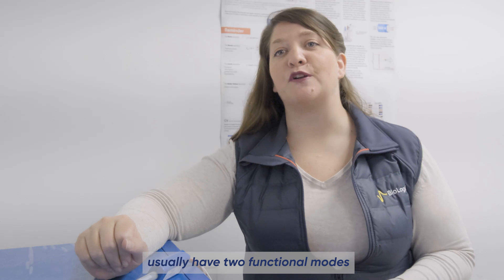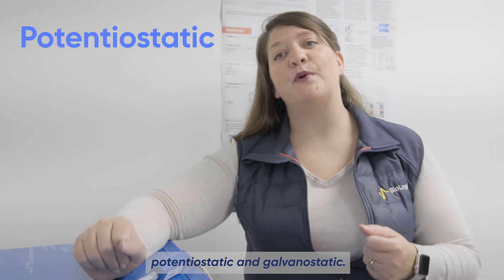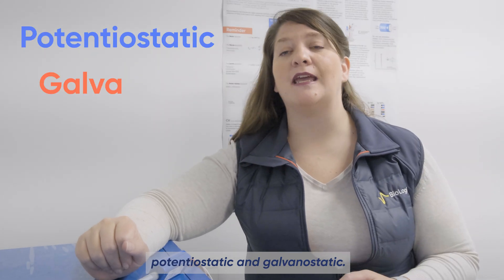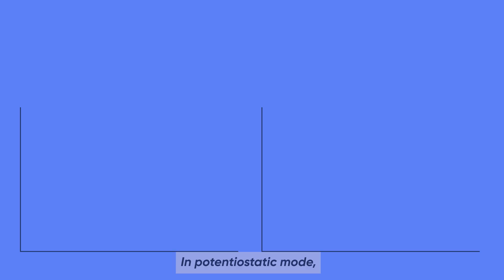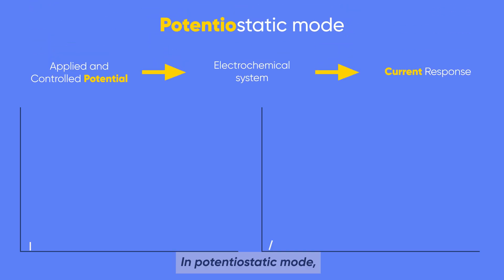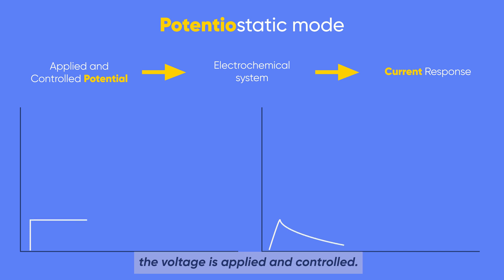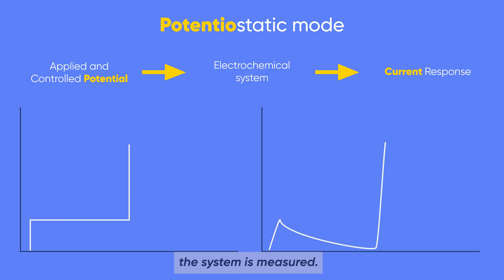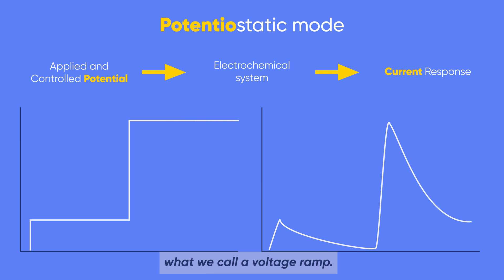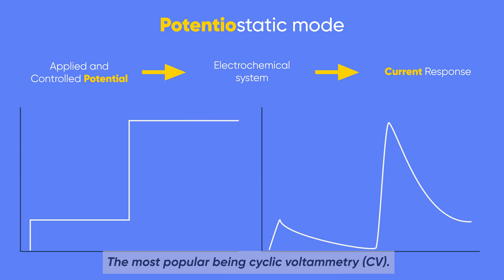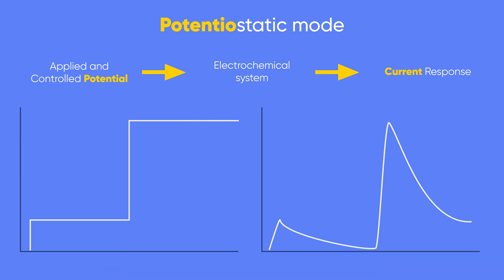These instruments usually have two functional modes: potentiostatic and galvanostatic. In potentiostatic mode, the voltage is applied and controlled, and then the current flowing through the system is measured. It is common to apply what we call a voltage ramp, the most popular being cyclic voltammetry.